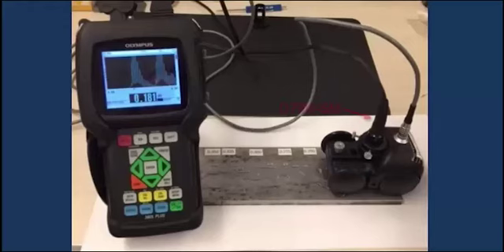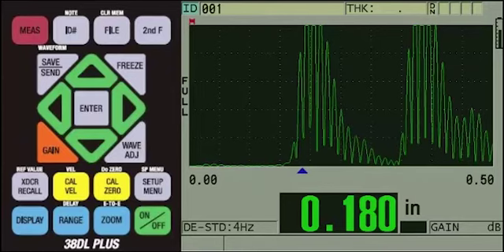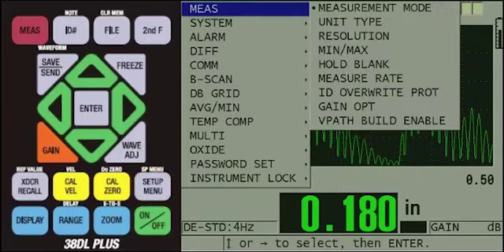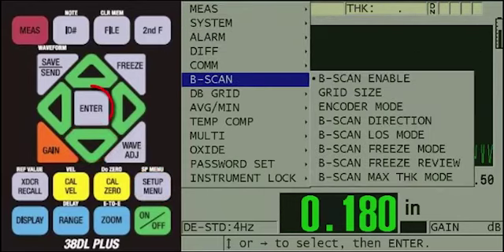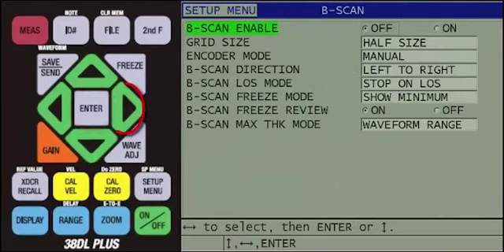Loosen the 2 set screws on the probe holder enough to allow the D790-SM to be inserted. Before tightening the 2 set screws, check the waveform display on the 38DL Plus to make sure you are getting good signals. If the signals on the waveform display look good, you can tighten the 2 set screws until they are holding the D790-SM securely. At this point, we can enable B-scan on the instrument. To do this, press the Setup menu key, then press the down arrow to highlight B-scan, and then press the Enter key. Use the right arrow to enable B-scan to on, then press the Enter key.